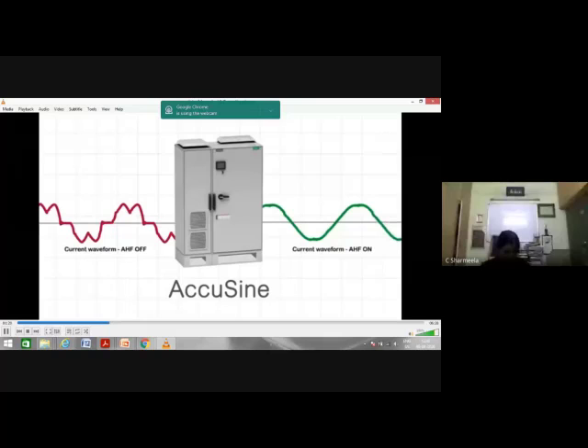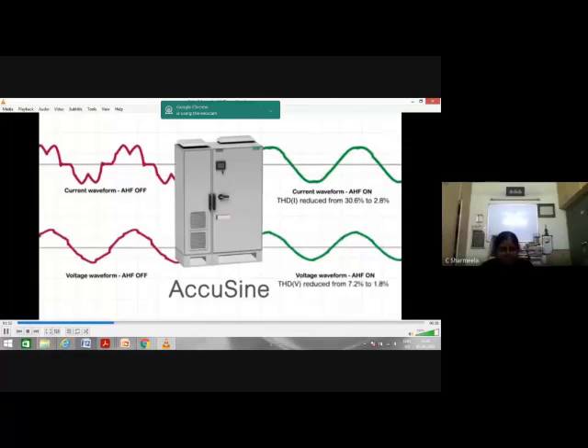AccuSine is ideal to remove the high-frequency current from your distribution network, which in turn reduces the voltage distortion by stopping the flow of high-frequency current through your electrical network impedance. The reduction of total harmonic distortion current and total harmonic distortion voltage removes the stress on your distribution network.